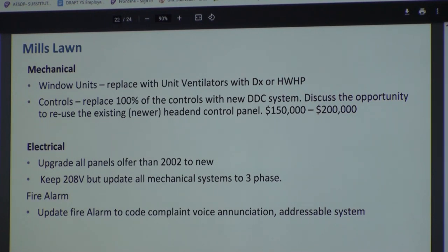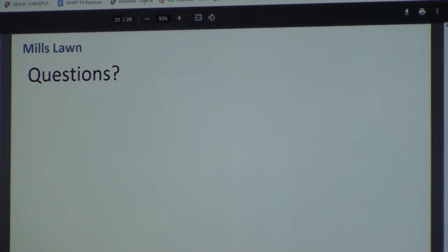Again, I think a control system would be a no-brainer. And on the electrical side, replace all the panels that are older than 2002. Again, I think you're married to the 208 unless you do a full renovation. And the fire alarm is also non-compliant - it's not voice annunciated, and the devices aren't addressable. So if you do a renovation, you would have to replace those.